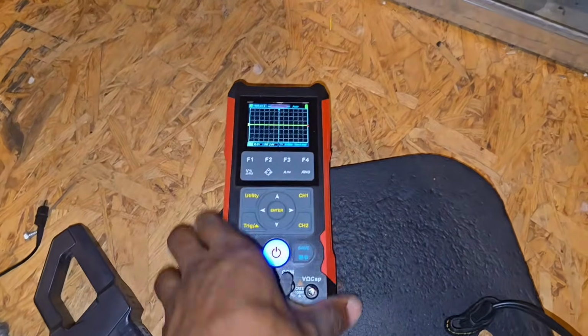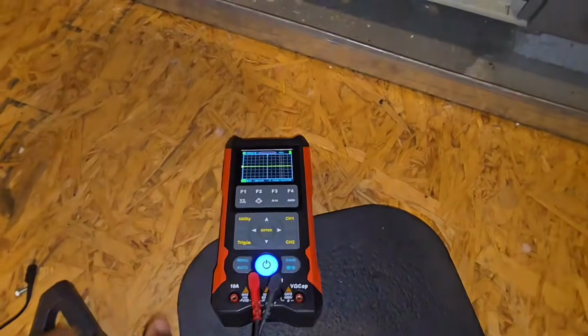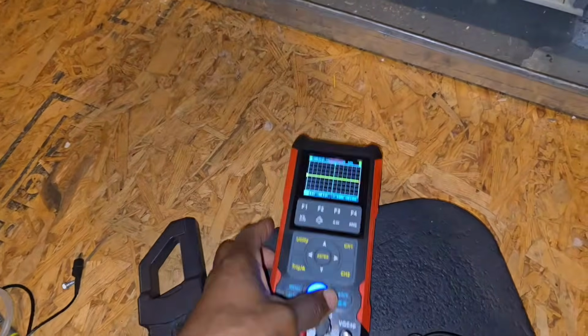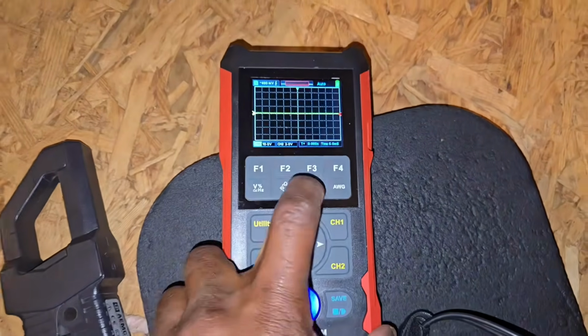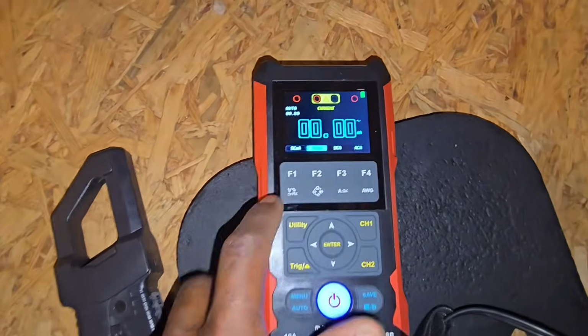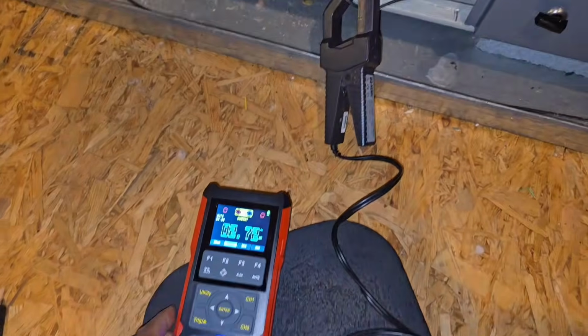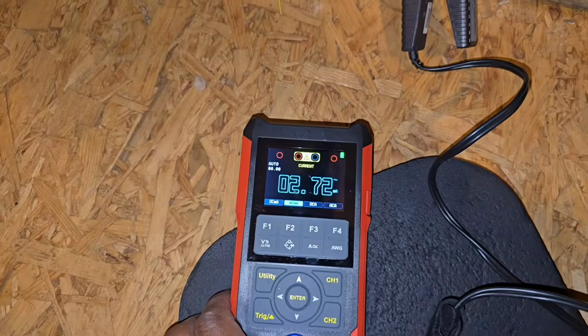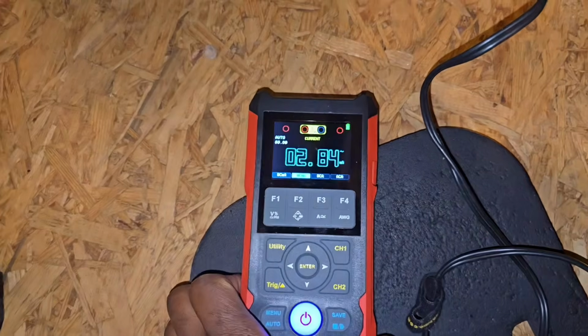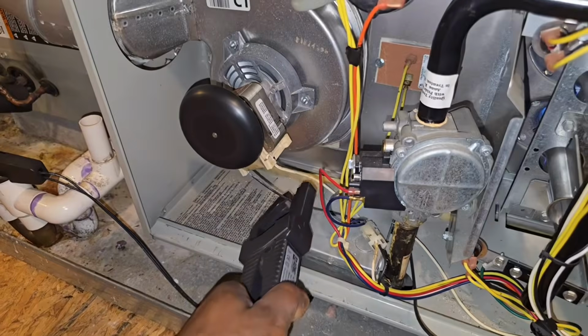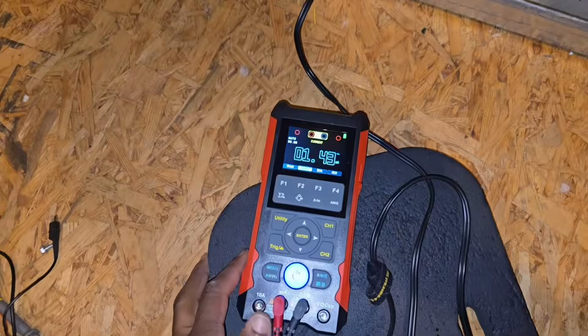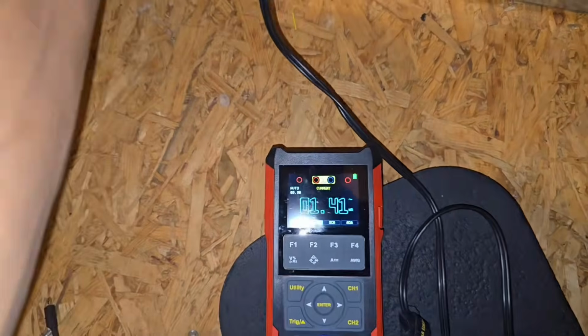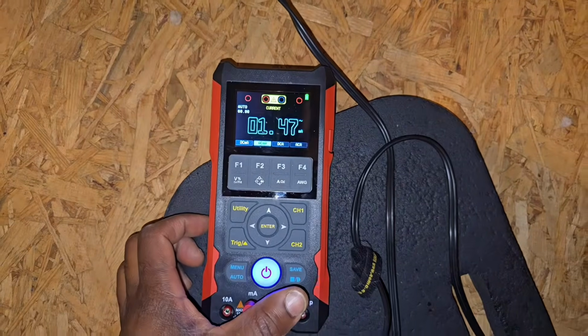I'm going to go ahead and check the current using the milliamp section and a current transducer. So we'll go to amps AC, put that into milliamps AC. Now I can take this current transformer, clamp that, 2.7. There you go. And we'll grab the amps for the inducer as well, 1.5.